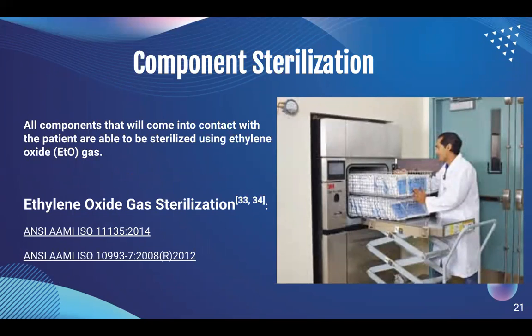All components of our device, including the needle, tubing, and adhesive, would be sterilized by ethylene oxide or ETO gas sterilization. ETO gas sterilization uses a combination of specific ETO gas concentration, temperature, pressure, time, and humidity. This type of sterilization is ideal for our device as the design includes polymers which cannot survive other sterilization conditions such as high temperature sterilization and UV sterilization. The sterilization of each component would be compliant with FDA regulations and the standards listed here on this slide.